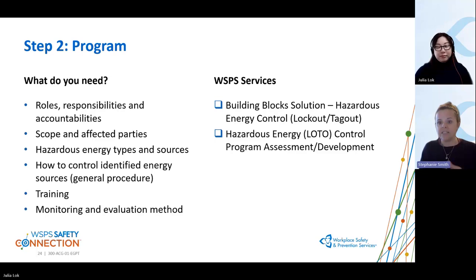That's key, and someone brought that up before: they don't know where the energy isolating devices are, and that's why we look to procedures. If you have equipment-specific procedures posted on your machines, you can go through and find that a machine has electrical, pneumatic, and gravity sources, and these are the steps to lock that out or control the energy sources. It goes into specific steps of how to do that, and oftentimes it tells you further information about the magnitude of the energy source if you need certain PPE. That's what we want to see with procedures.